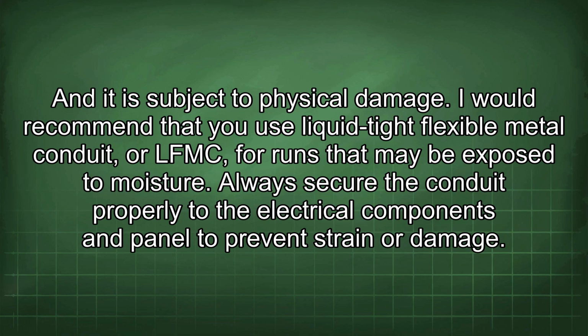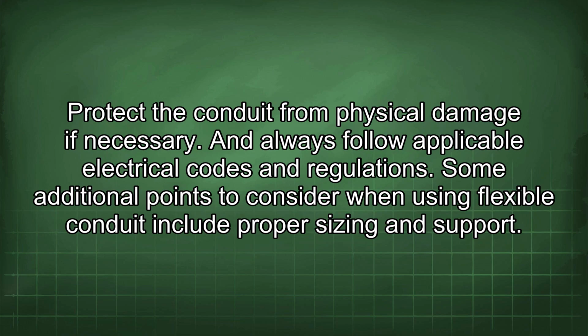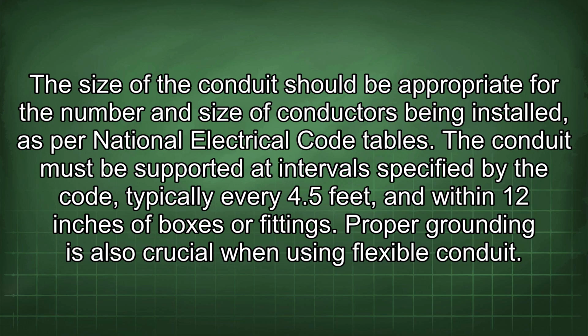I would recommend that you use liquid-tight flexible metal conduit, or LFMC, for runs that may be exposed to moisture. Always secure the conduit properly to the electrical components and panel to prevent strain or damage. Protect the conduit from physical damage if necessary, and always follow applicable electrical codes and regulations. Some additional points to consider when using flexible conduit include proper sizing and support. The size of the conduit should be appropriate for the number and size of conductors being installed, as per National Electrical Code tables. The conduit must be supported at intervals specified by the code, typically every 4.5 feet and within 12 inches of boxes or fittings.